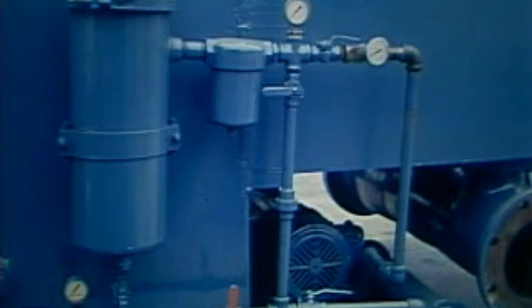Remember, you should flush the pump anytime you find contaminated oil in the crankcase. When you do this, change the cartridge filter element and clean the magnetic filter before and after flushing. It's recommended that you follow the diesel with lightweight motor oil during flushing to eliminate the diesel, which has no lubricating value and will dilute the lubricant. Follow the instructions of your senior engineer concerning this procedure.